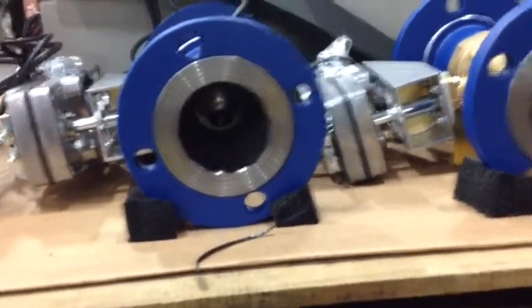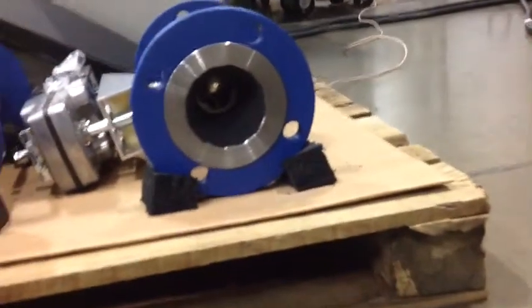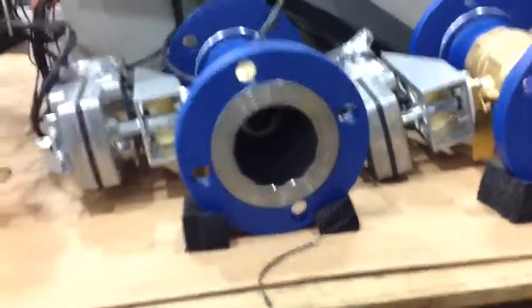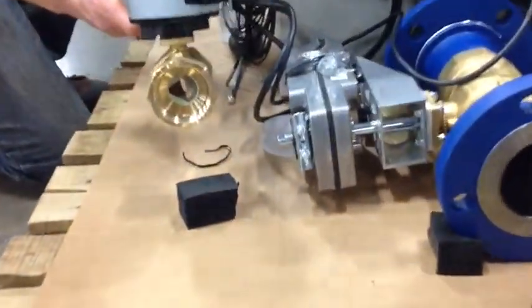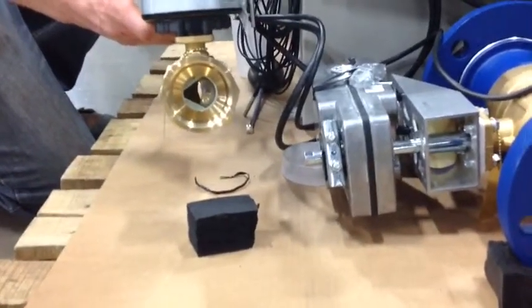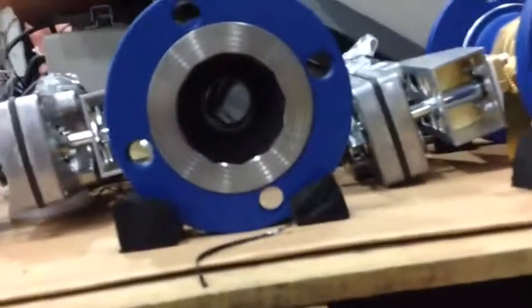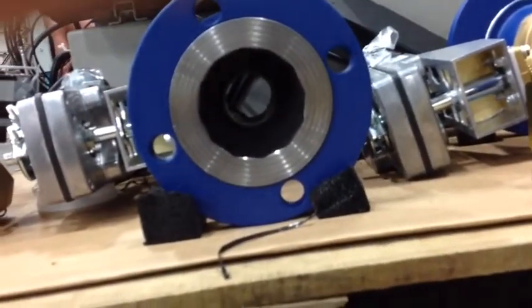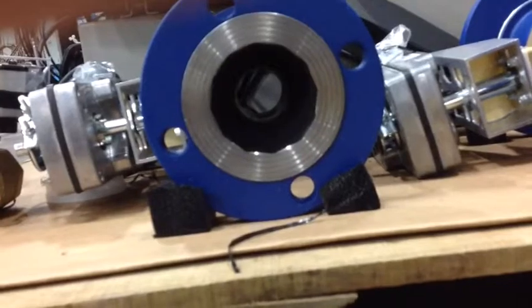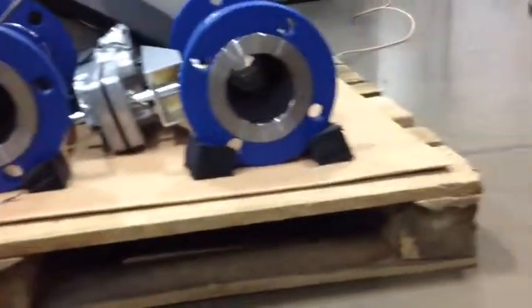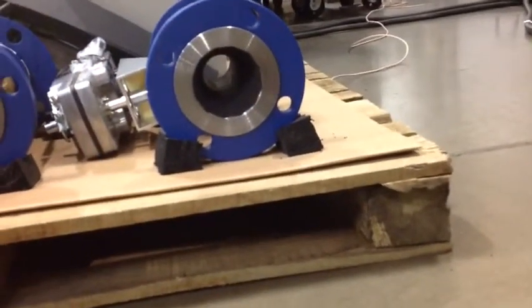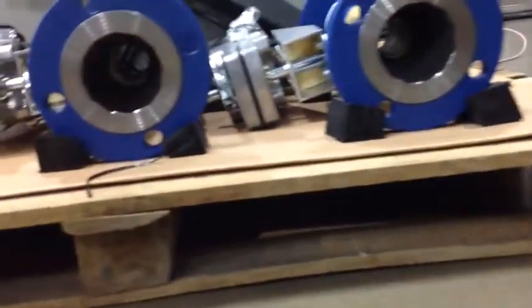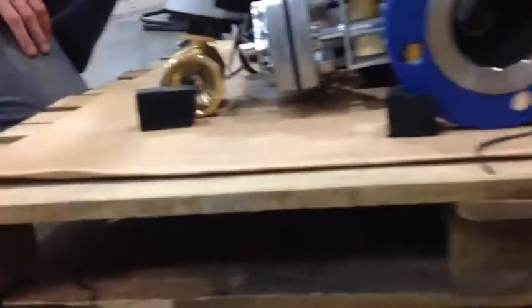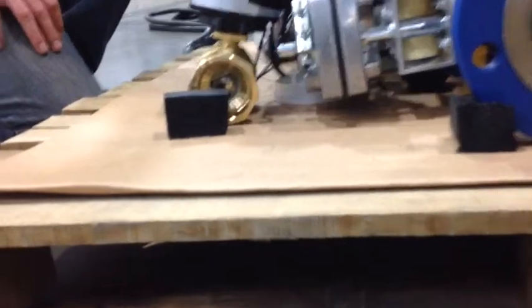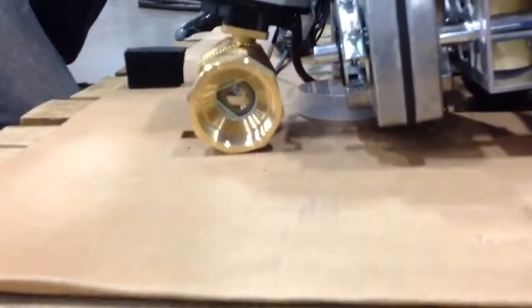You can see the shiny part of the closed part of the valve, and these are the isolation valves that come from the building loop. So now we'll slide over and observe the valve is closing and the isolation valves are now open, so they've stroked open. What caused that was placing the entering temp sensors into a cup of ice water.